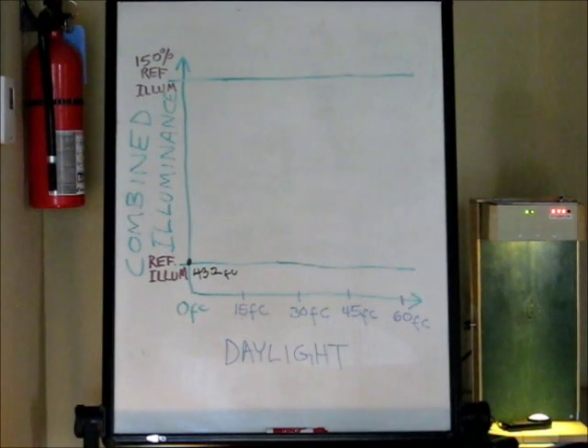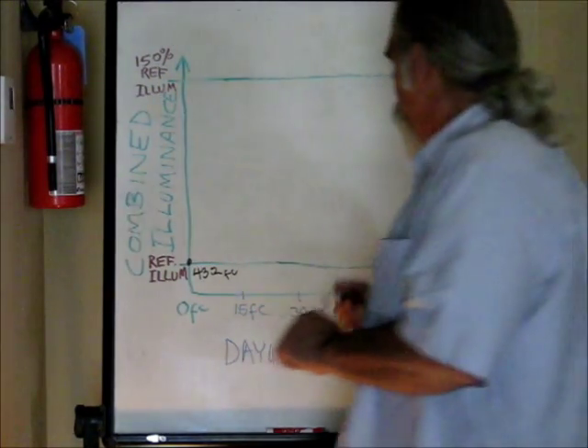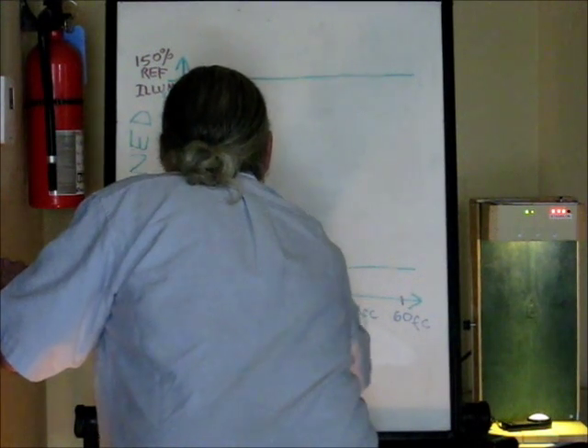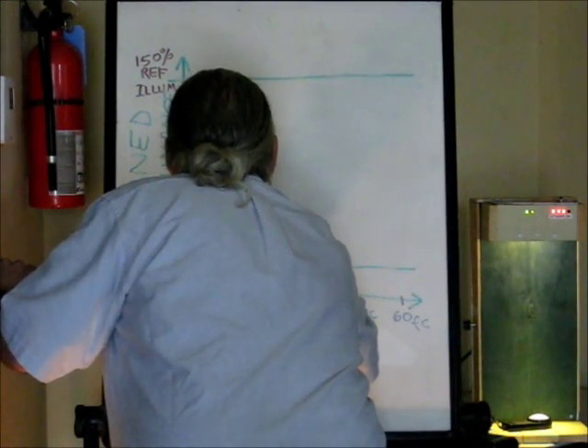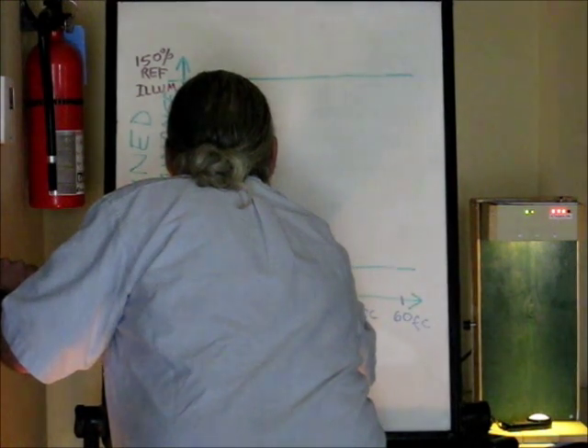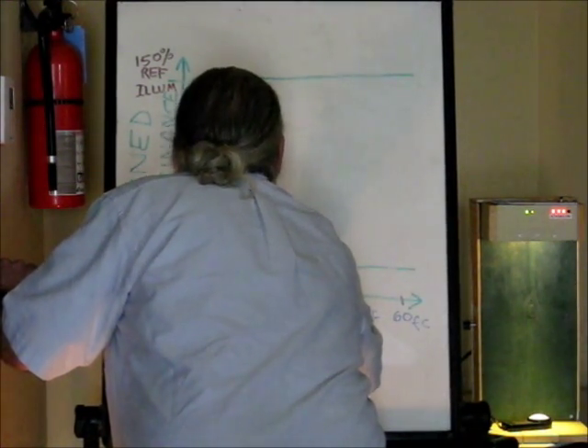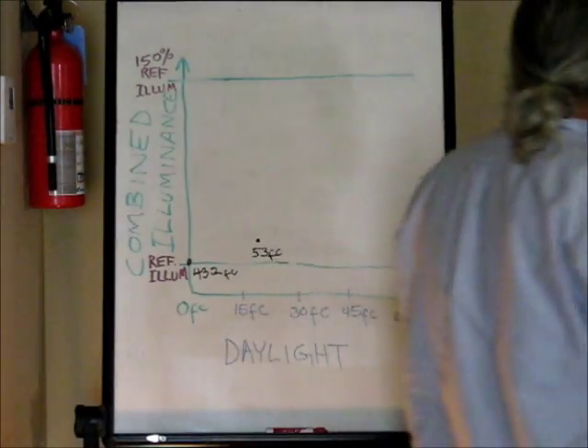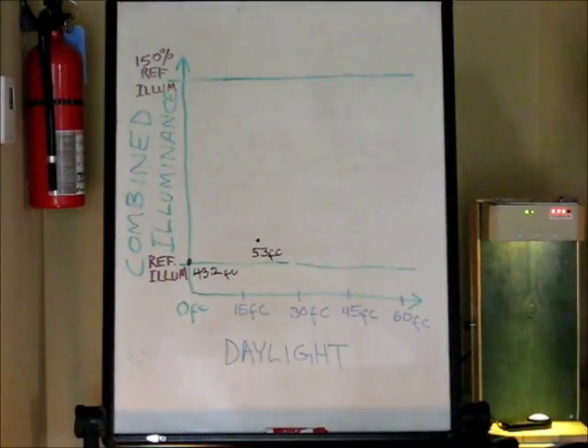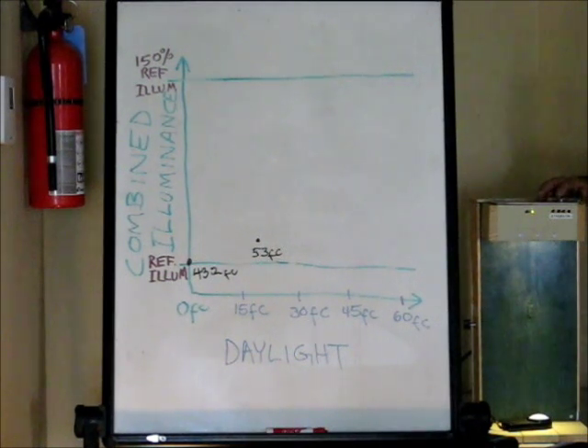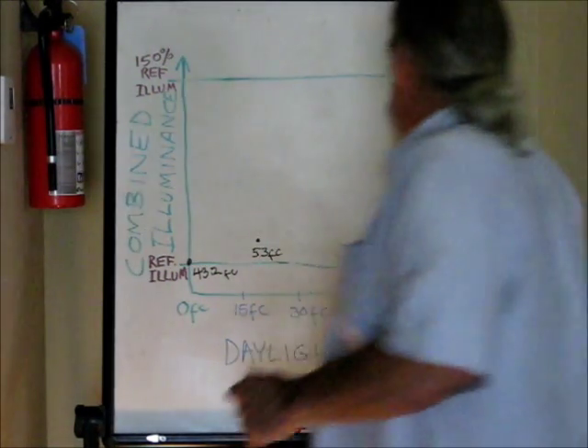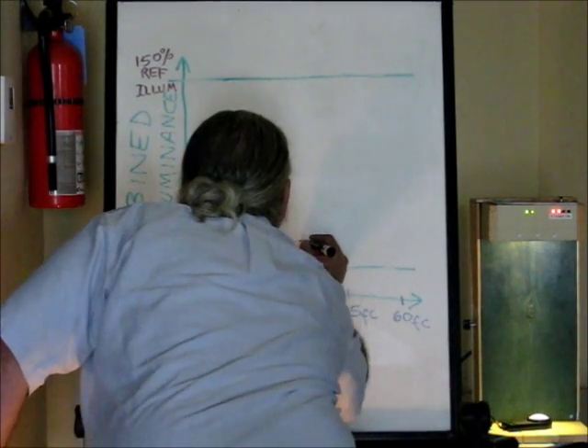We'll call it 53 total. So at about 20 foot candles, I've got about 53 foot candles combined illumination. This is both electric and daylight in the space. And we're just going to repeat this. We're going to turn our simulator knob clockwise until we just get it to snap off again. I've got 52 at about 31 daylight. So I've got 52 foot candles at about 31 daylight.